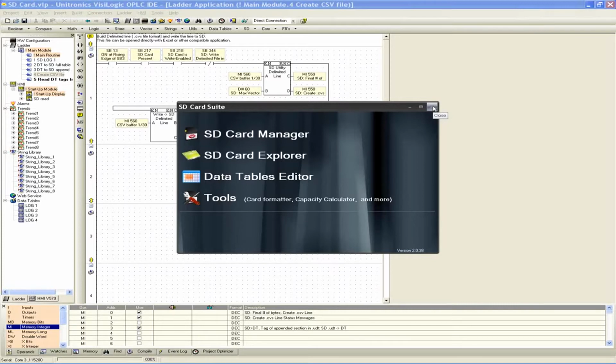I can't show you that on remote access. Information mode isn't supported in online test mode here, but I can tell you, if you go into information mode, you enter your default password on your PLC. To get into information mode, you hold down the touchscreen for 4 seconds. It'll ask you for a password. The default is 1111. And then you'll see there's an SD menu that you have options available for, and there you can select to clone and download it to the SD card or upload it to the PLC.